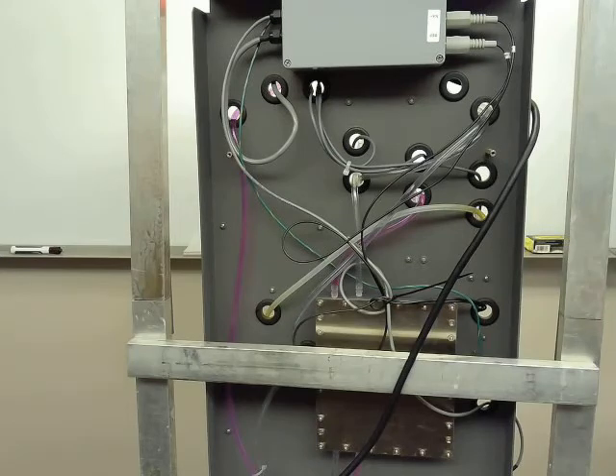In terms of probe life, a measuring probe should last about one to two years, I would say. There are certainly places that want to proactively replace them on a yearly basis, but there are also probes running for three or four years, no problems. For me, if it's passing calibration, most likely the probe is good, and there's no reason to replace it. That regen process, each time you do it, does decrease the overall life of the electrode.